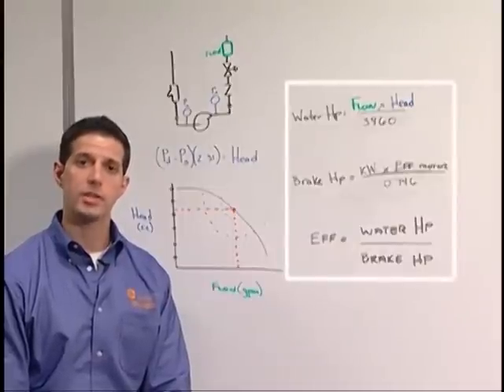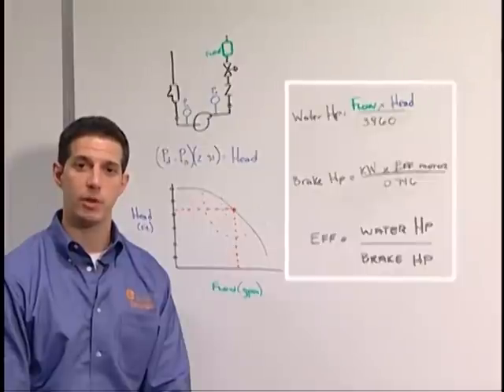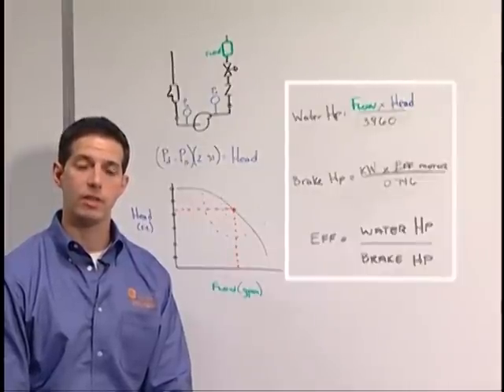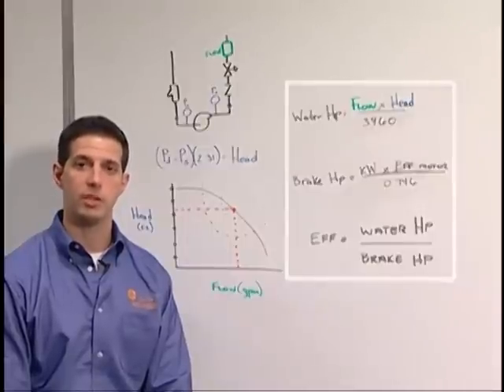Brake horsepower is calculated by taking the actual tested readings in KW, multiplying that by the nameplate motor efficiency, and dividing that by .746. The difference between the water horsepower and brake horsepower is the efficiency.